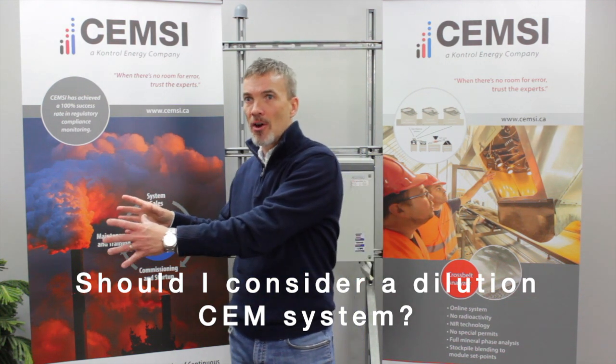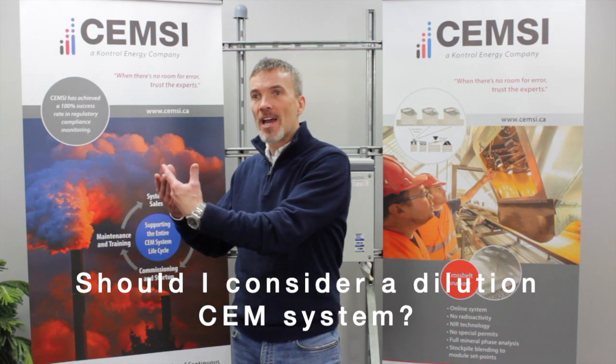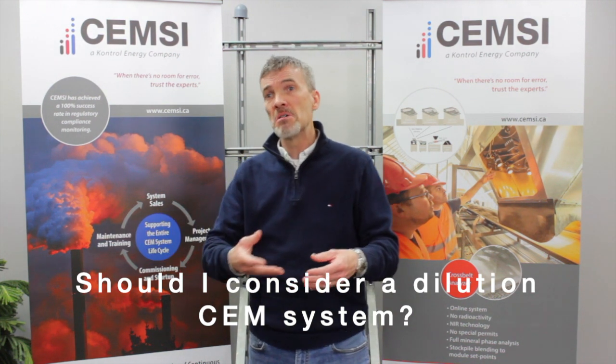When it comes to dilution, the advantage of dilution at the time was when you're dealing with really high concentrations of SO2 and NO and CO and all those gases, what you can do is, by having a very good air cleanup module, which costs more than most analyzers, you create this dilution air and you dilute the sample coming down. And it has two effects. One is it reduces the amount of high concentration gas coming down to your analyzer. It cuts it by, depending on your dilution ratio, 50 to 1 or 100 to 1. So if you ever did have a leak of this gas, it's not overly toxic. You're not bringing thousands of ppm down, you're bringing tens of ppm down.